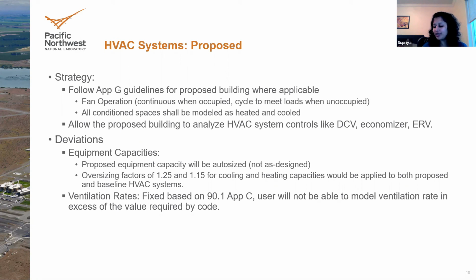So just to summarize, Gail, we will add an exception for DOAS systems. Where we say in the applicability criteria that multi-zone systems cannot be analyzed, we'll say except DOAS. For DCV, it looks like we want the same thing we discussed for lighting controls, where we identify the percentage of ventilation rate reduction based on building area types, which can be used for the building area type approach. When a user specifies the space-by-space breakdown, we can model the actual ventilation rates and adjust for DCV control.